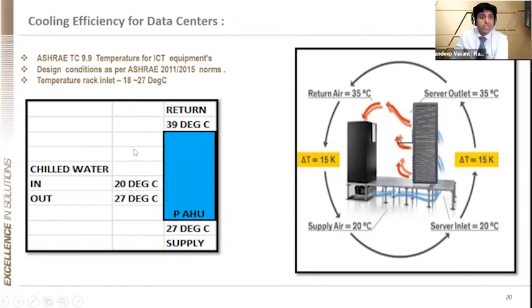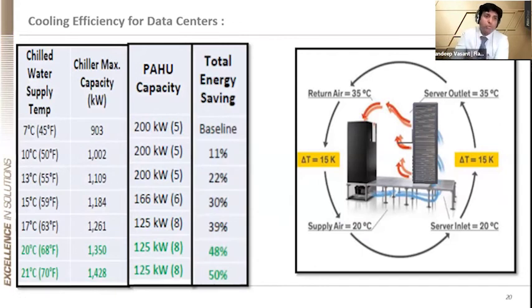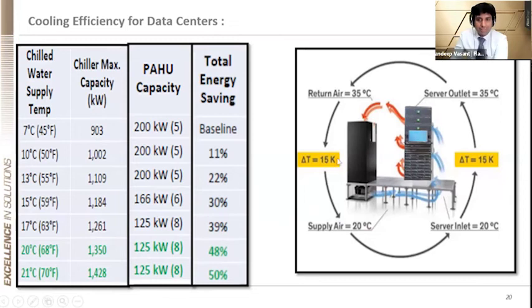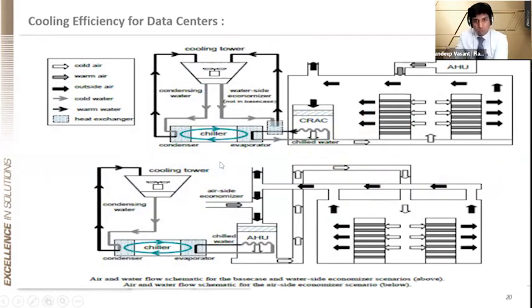With this methodology, the chilled water temperature from the chiller can also go high. So here is the typical methodology. So not only do you get a saving on the PAC, but also on the chiller. Case study of a chiller: let us say driving the chiller at a 21-degree outlet vis-a-vis 7-degree, you get a saving of 50%. So this is something which we can also implement in the chiller. As I talk, you can see the PAC and the server rack supply and return, which I explained in the earlier slide. So a combination of both air side economizer and water side economizer, basically choosing the right PAC unit and the chiller with the free cooling, direct free cooling, indirect free cooling, would give you the best in class efficiency, would obviously increase the COP and decrease the PUE number.